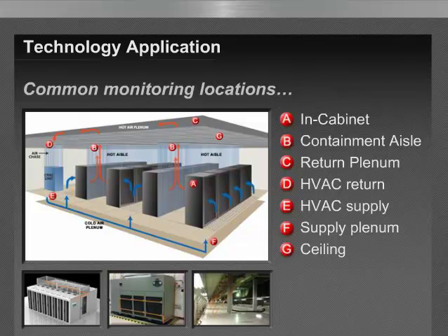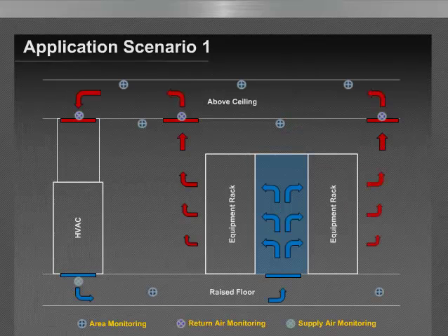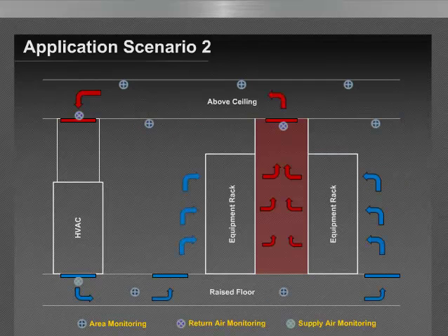And the following slides here are just some examples of that very same configuration. Each of them shows a different hot aisle configuration, just to show, as you'll see, a common theme for each and every one of these examples, that we're following the airflow. And that's the beauty of an air sampling type and aspirating detection technology, is that you can place sampling at the locations where air is going to gather and use that as a logical location for sampling and detecting smoke.